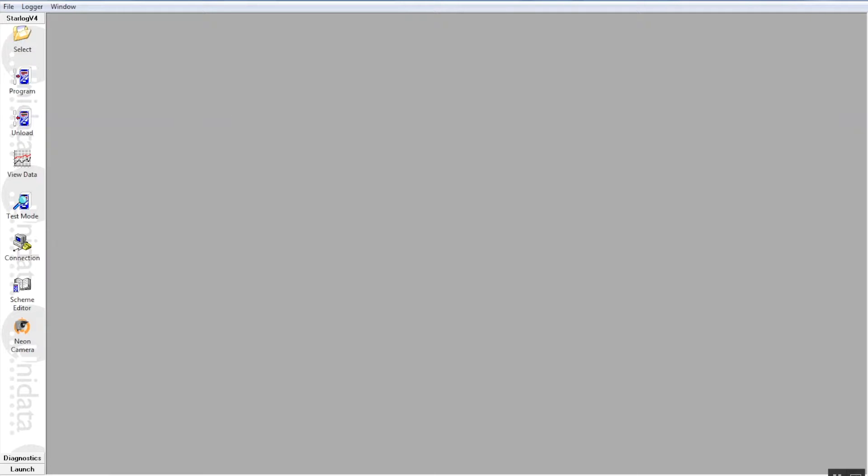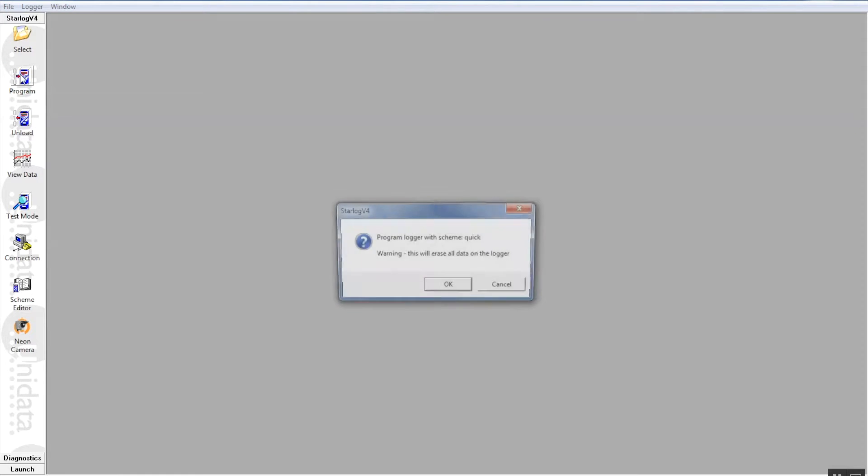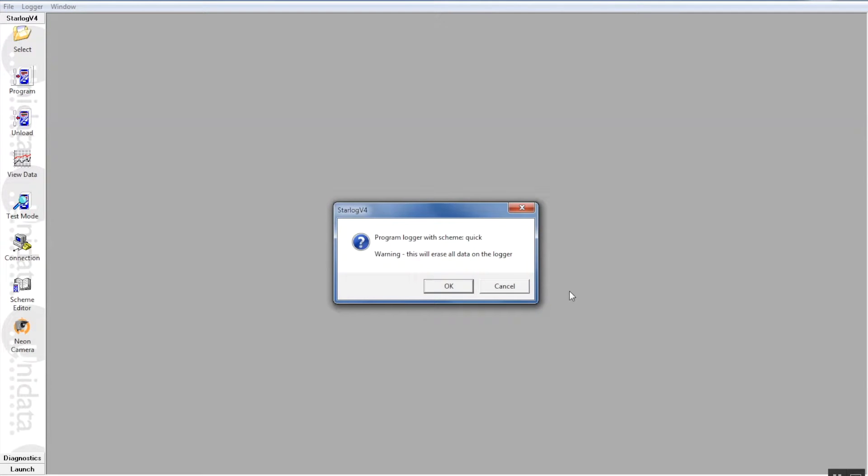What we need to do now is we need to program that scheme or upload the scheme to the starflow instrument to make it work. So over to the left hand side of the screen again and we press the program button. Now this will bring up a dialogue screen to warn you that all data on the starflow instrument will be lost. So what it does basically is it resets all the counters, all the pointers and the software areas so that it is ready for the new scheme.